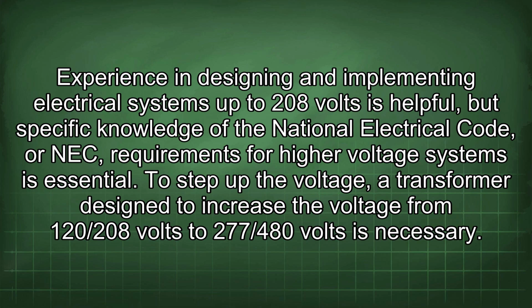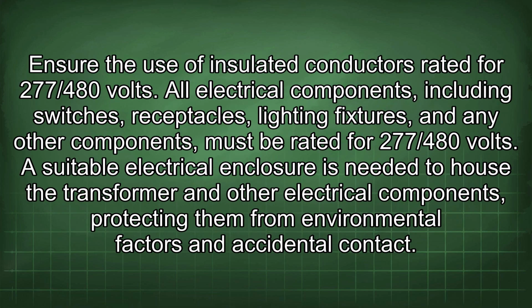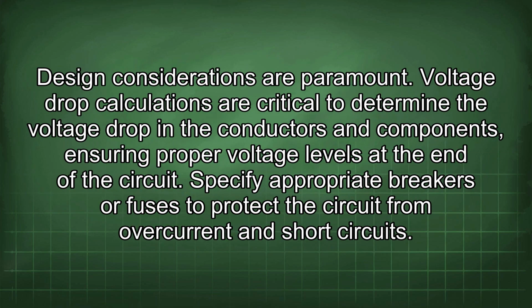To step up the voltage, a transformer designed to increase the voltage from 120/208 volts to 277/480 volts is necessary. Ensure the use of insulated conductors rated for 277/480 volts. All electrical components, including switches, receptacles, lighting fixtures, and any other components, must be rated for 277/480 volts. A suitable electrical enclosure is needed to house the transformer and other electrical components, protecting them from environmental factors and accidental contact. Design considerations are paramount.